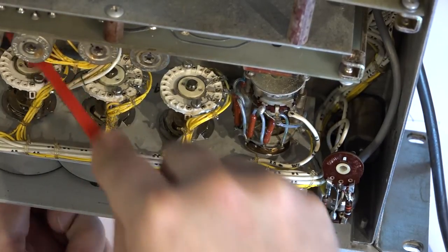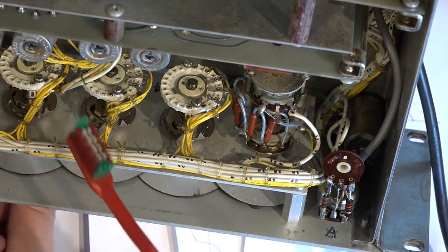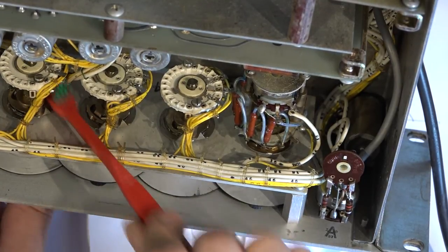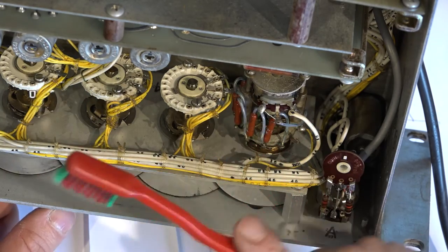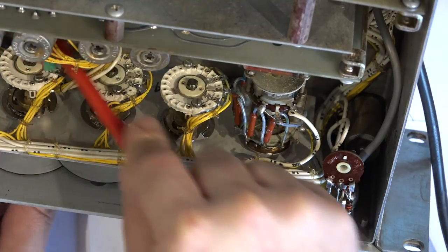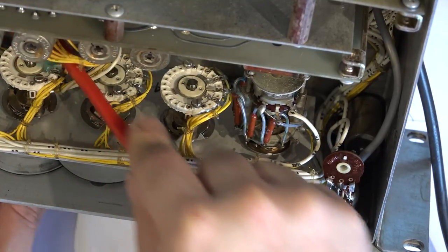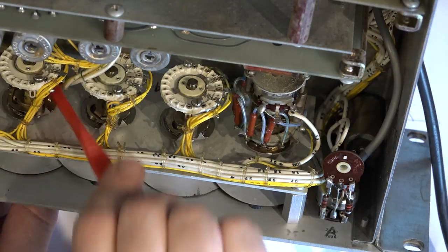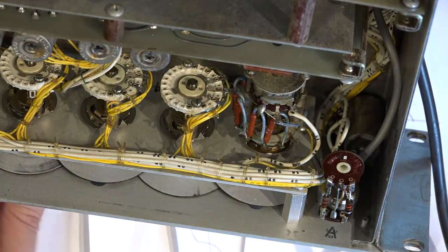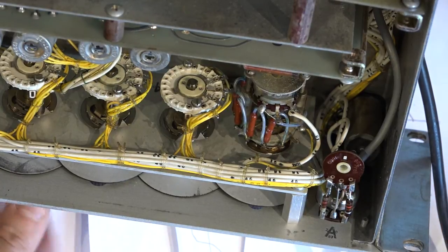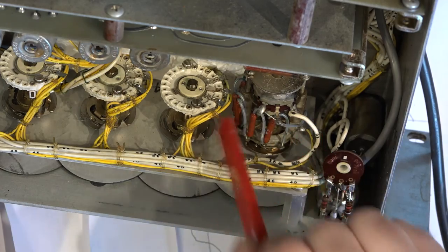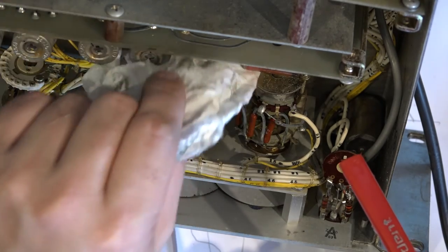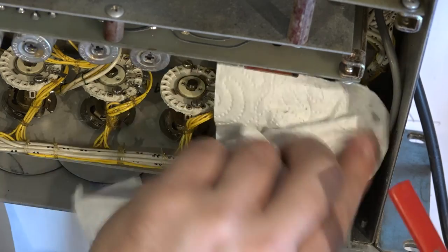And if you are not happy with the results, of course you can do more cleaning on it, but I think it's okay. In my case, it looks absolutely like new. And lubrication, yeah there's enough lubrication on it. And let me also clean a bit on the bottom. Yeah, really nice, good, good. Of course, there are other chemicals on the market, some kind of gold and I don't know. But let me tell you, in these high voltage devices, it's absolutely a wrong idea to use this gold feedthrough solutions because it can leave a tiny tiny layer from gold on everywhere. So the high voltage can really run from one pin to the other. But you don't have this issue with the vaseline.